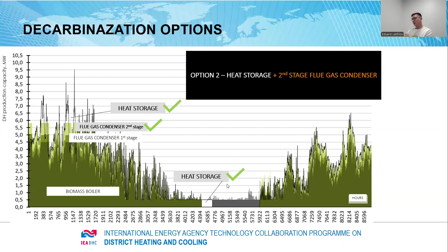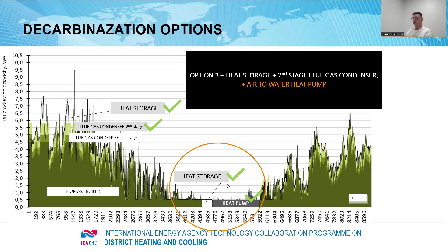To solve that, we can also install an air-to-water heat pump to run during summertime, combined with heat storage — which works perfectly. The heat pump's COP is quite high in summer, so in combination with heat storage we can run it, for example, during the nighttime when electricity prices are lower, pump heat into storage, and optimize the heat price for consumers. This is one of the solutions.